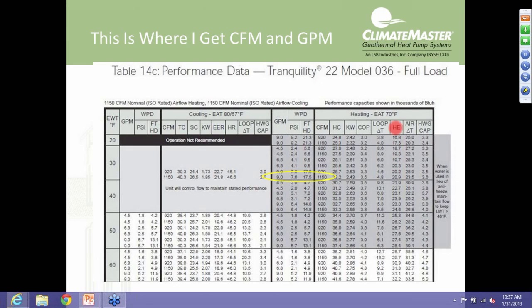We always do water side analysis first before we ever put gauges on the heat pump. The only exception, of course, is our split systems. We've got to charge them because now we have a field installed line set between the compressor section and the air handler section.